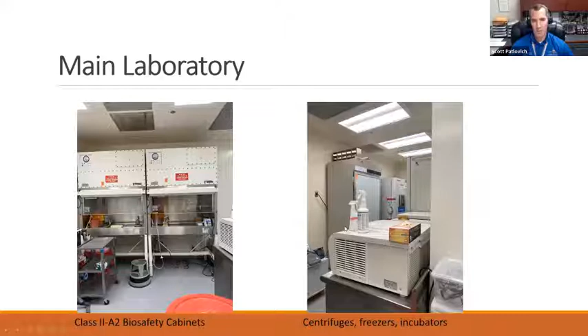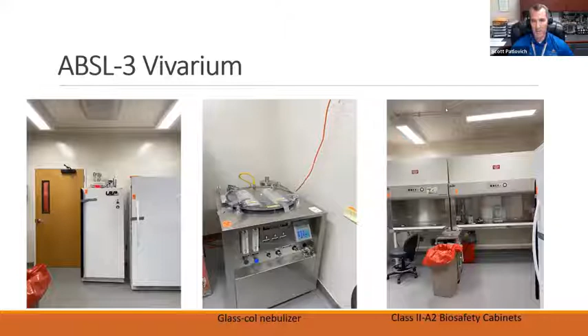This is looking into the ABSL-3 space. You would enter through this door, and this is what it looks like inside. The picture on the left has 2 freezers. The center picture is a nebulizer, so you can actually place research animals into a little basket down into this sealed, gasketed, covered piece of equipment. You can actually nebulize Mycobacterium tuberculosis, SARS-CoV-2 into that chamber and allow the research animals to breathe in those pathogens as part of the experimental infection process. And then on the right, 2 additional biosafety cabinets for manipulating any animal cages with infected animals in that space. These are the individually ventilated cage racks that are HEPA filtered and exhausted, no air recirculation whatsoever. Each of these little rack spaces would have individual cages when animals are actually in that space.